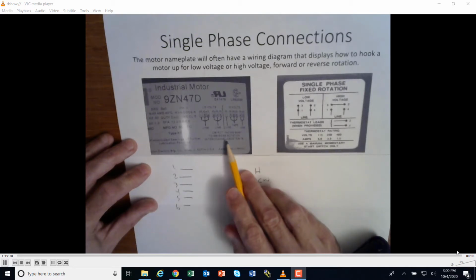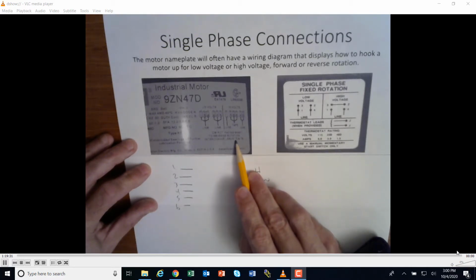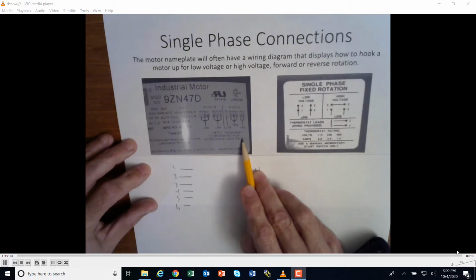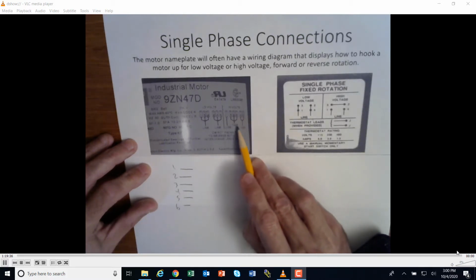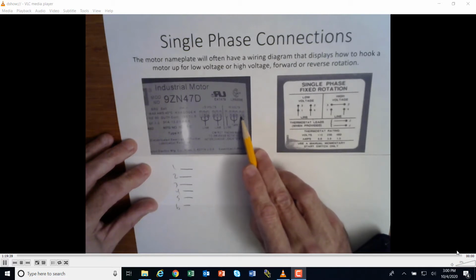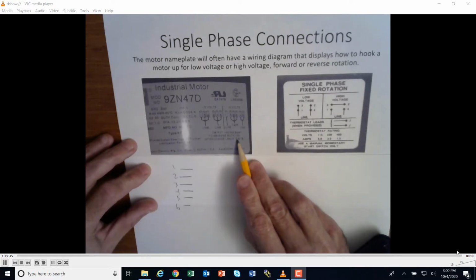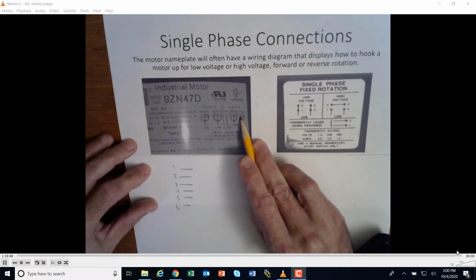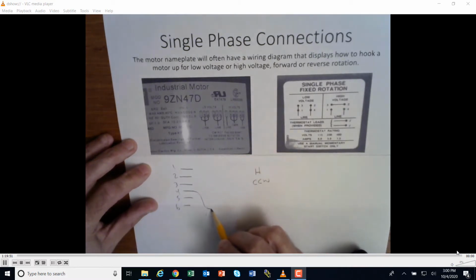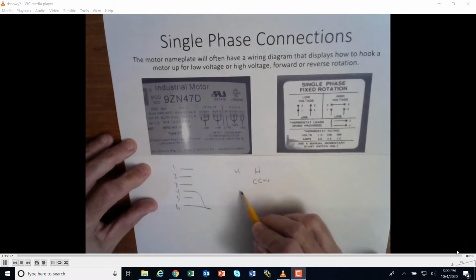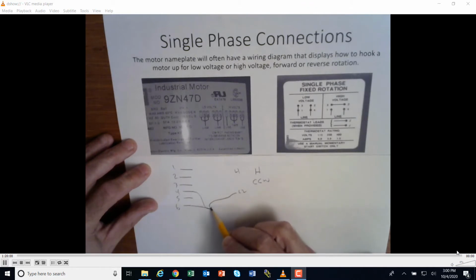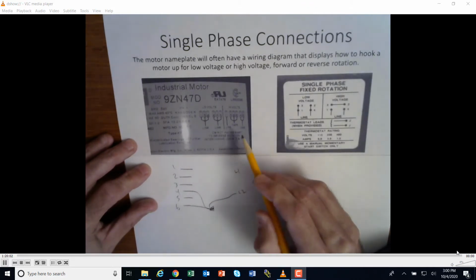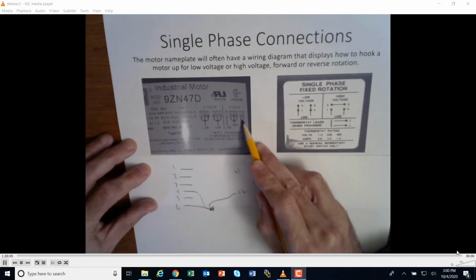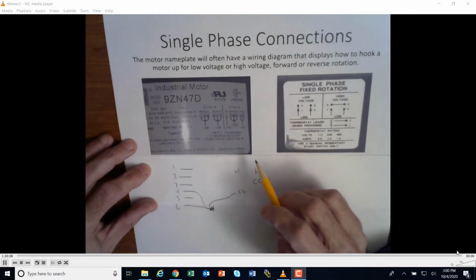And so we would interchange leads 5 and 6. So this is shown as clockwise, so it says 4 and 5, but because we're running the other way, we are going to interchange 5 and 6. So we're going to go 4 and 6. So according to this, 4 and 6 would come here, and we have line 1 and line 2. So line 2 would come here, and then this would get wire nutted together and taped, and then therefore we have brought a line to 4 and 6 instead of 4 and 5 because we're going the other direction.